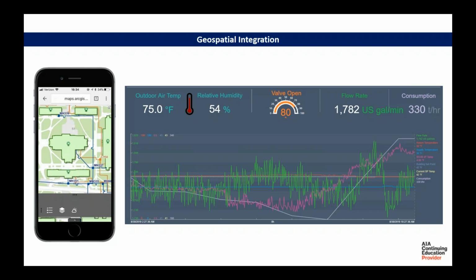What we want to do now is move towards operational intelligence, using analytics like before. Continuing this example, we know there's a correlation between chilled water consumption, temperature, humidity, and wet bulb temperature. So we have models built within the PI system that automatically update, giving us expected performance versus actual performance over time. We compare the two and create an alert if there's a non-standard event.